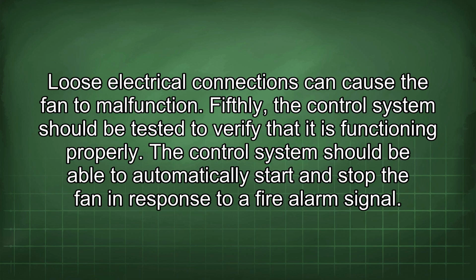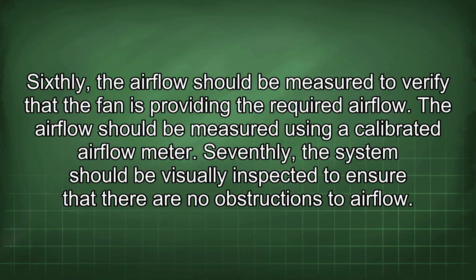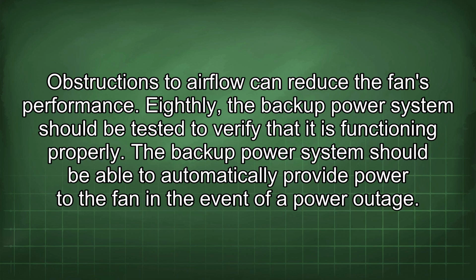Fifthly, the control system should be tested to verify that it is functioning properly. The control system should be able to automatically start and stop the fan in response to a fire alarm signal. Sixthly, the airflow should be measured to verify that the fan is providing the required airflow. The airflow should be measured using a calibrated airflow meter. Seventhly, the system should be visually inspected to ensure that there are no obstructions to airflow. Obstructions to airflow can reduce the fan's performance.